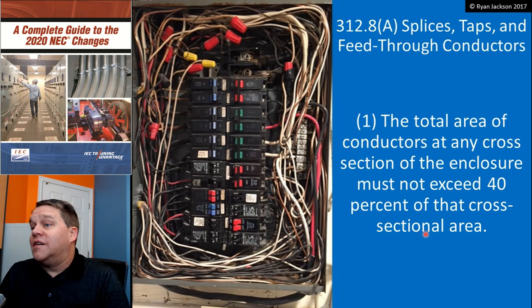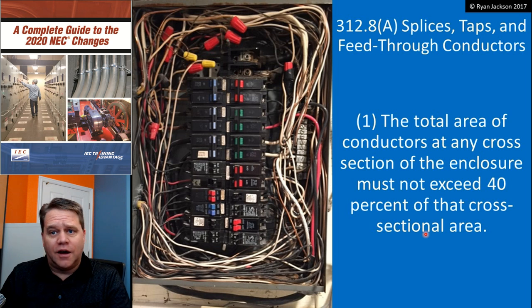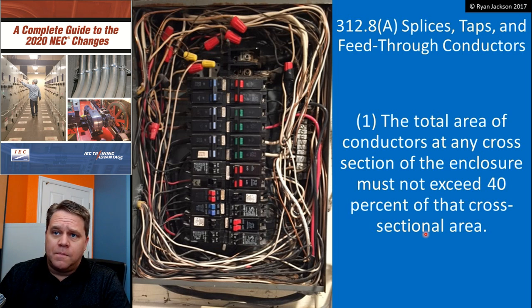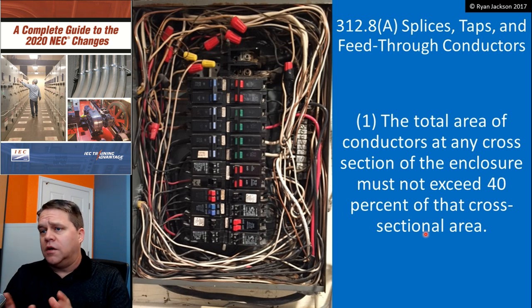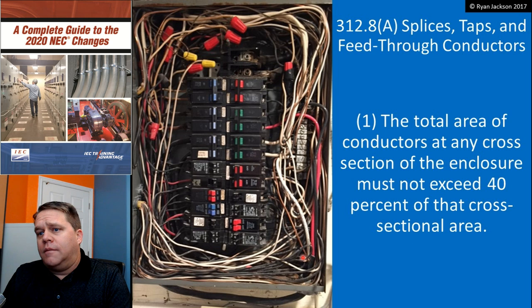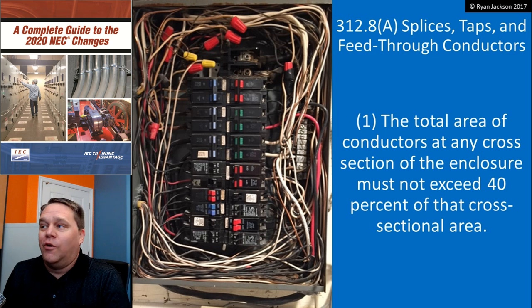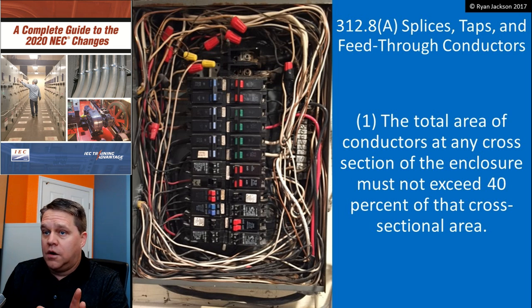Starting with A1 — the total area of conductors in a cross-section of the enclosure must not exceed 40% of that cross-sectional area. Now you may think you've seen some ugly panels, and perhaps you have — I certainly have. But regardless of how ugly your panel was, you did not see a violation of this section. I'm seriously not kidding — I don't think you can actually violate this section. I think it's impossible. It's not a challenge; I'm not telling you to go prove me wrong.